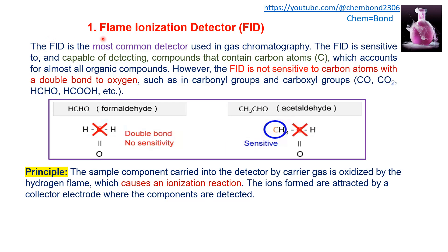The first detector is the flame ionization detector (FID). FID is the most commonly used detector in GC. It is sensitive to and capable of detecting compounds that contain carbon atoms, which accounts for almost all organic compounds. So FID can be used for all organic compounds, but there are some exceptions — it is not sensitive to carbon atoms with a double bond to oxygen, such as carbonyl carbon and carboxyl groups.